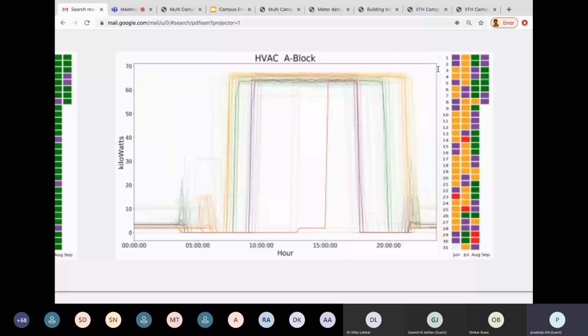But there is a schedule. Now, is the schedule properly maintained or not? That we can see. On the right side, the purple color indicates the holidays, June 1st and June 2nd, Saturday, Sunday, like that. On holidays and weekends, the AC should be switched on at 10 o'clock and switched off by 5 o'clock. So that's what we can confirm here.